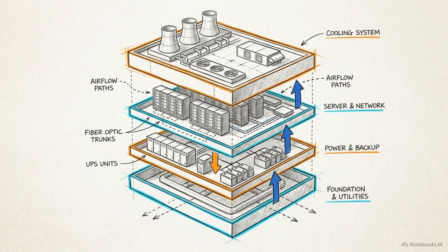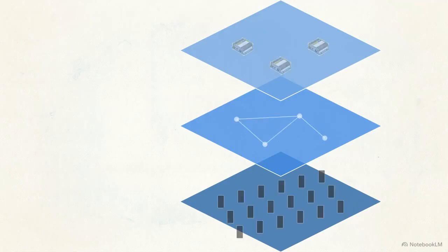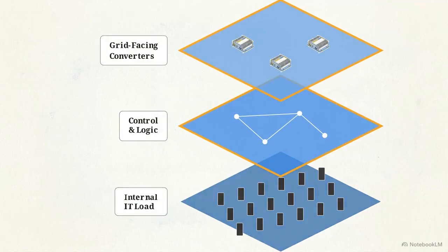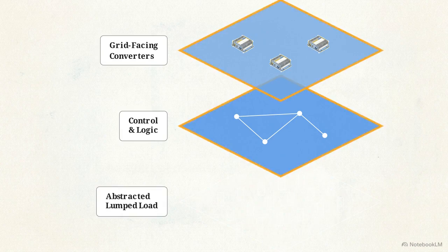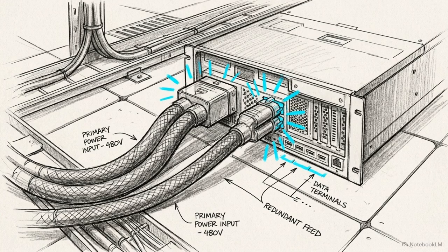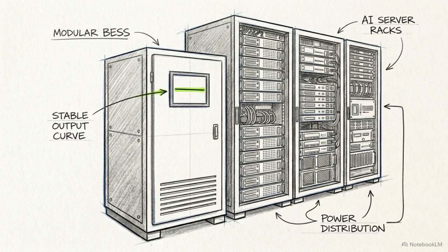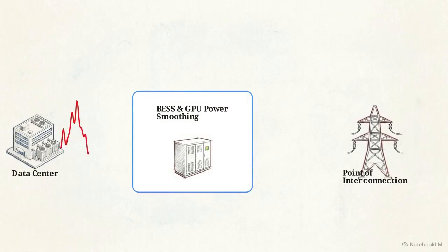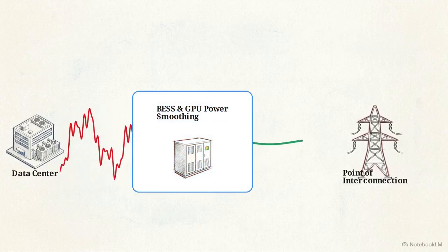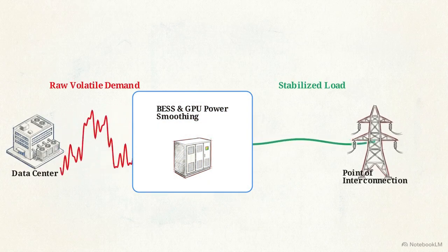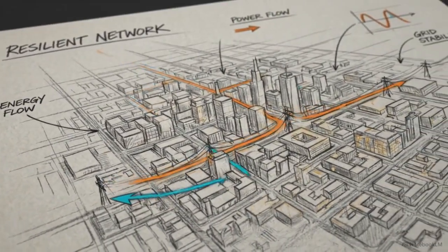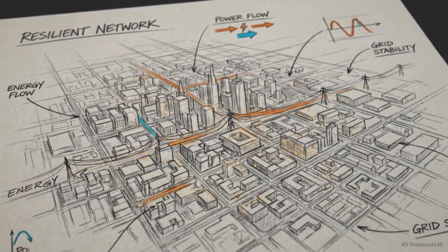To manage this complexity, engineers use a modeling in layers philosophy. This approach represents only the specific control loops and grid-facing converters that shape the disturbance, while abstracting the internal facility components that do not impact the grid. Beyond modeling, data center developers must implement localized hardware mitigations to dampen these intense power fluctuations. This image shows a rack-level battery energy storage system. These units provide a perfectly smoothed power output, absorbing fluctuations before they can reach the grid. These fast-acting grid-forming batteries, combined with GPU software power smoothing, act as a buffer to dampen oscillations before the point of interconnection. EMT simulation provides the mathematical lens required to engineer these defenses and maintain the integrity of an AI-powered grid.